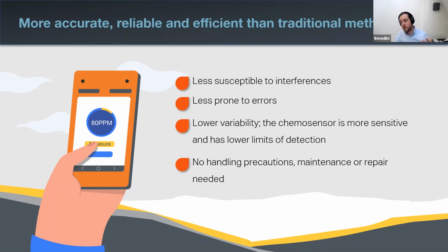Since every measurement uses an extra, single, individual cartridge, which are individually quality controlled, there is no carryover or inclusion of systematic error. For example, if you look at the electrode or reagent solution in an automated analyzer, which could have an error or a mistake, that would carry over through your whole measurement process without the operator necessarily being aware of it.